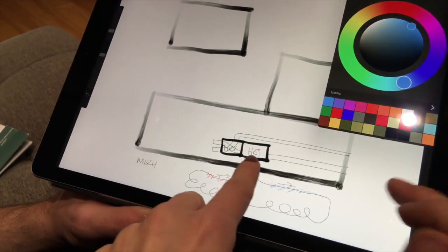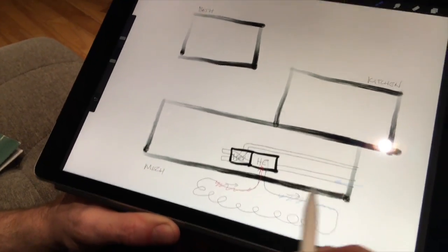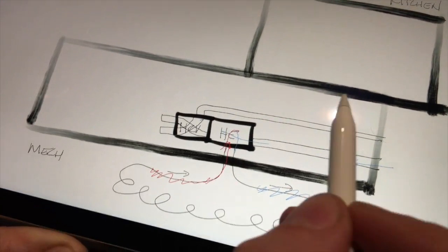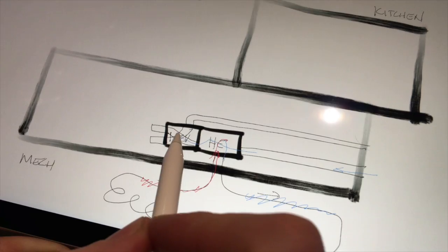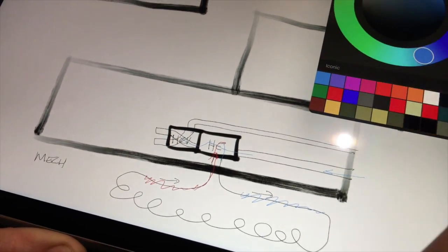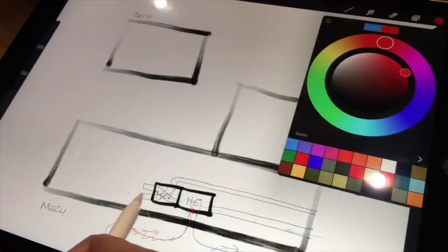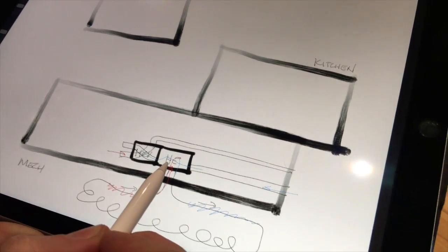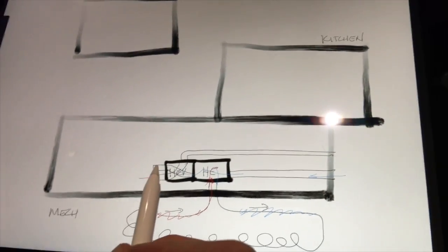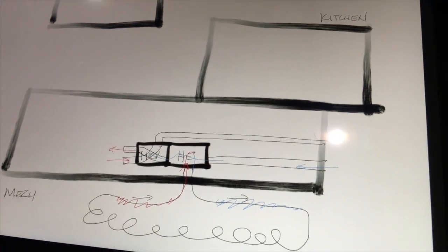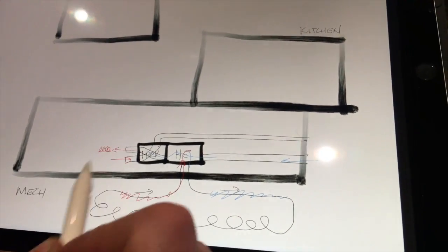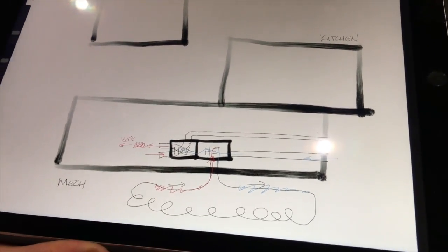So this guy carries on. This brings cold air in. It passes through the heat exchanger. It warms it up a little bit, so it's semi-warm. And then it crosses it with the air leaving the house, which is warm air, right? Warmer than outside. So that heat and this heat up this air so that by the time it's coming into the house, it's warm. And we've got a little electric resistance heater that goes here to raise it to 20 degrees Celsius. That's our heating system and our fresh air system.